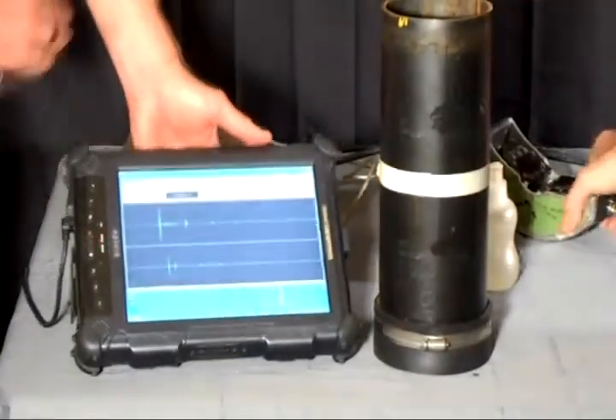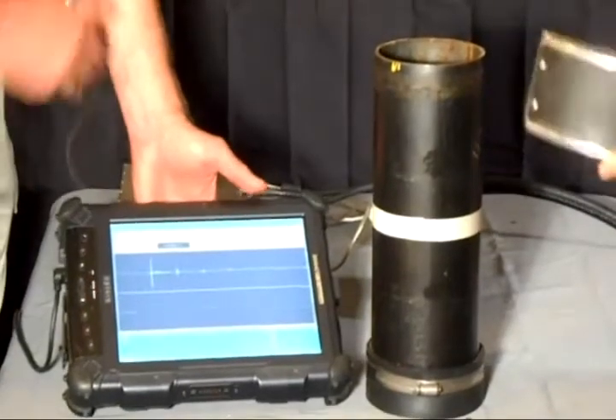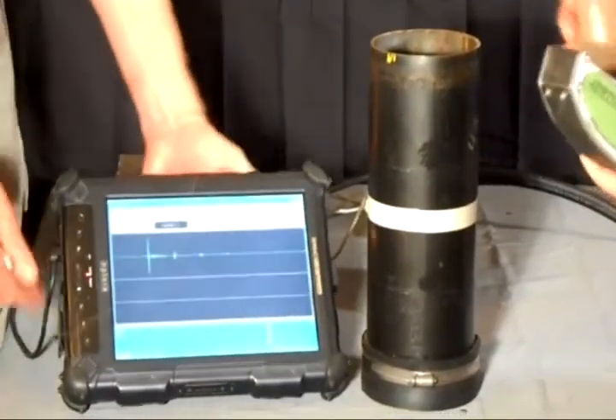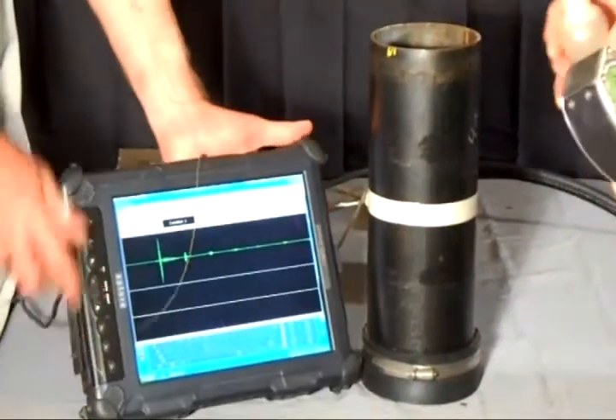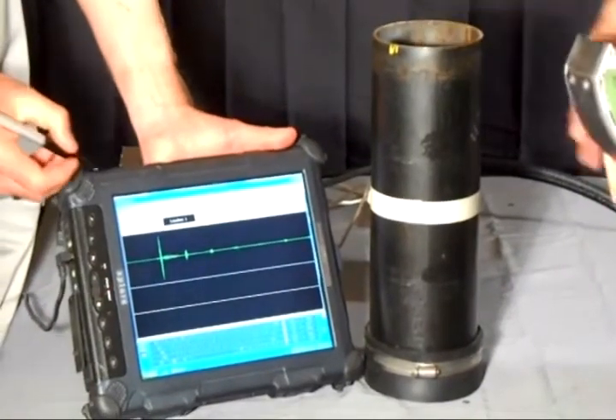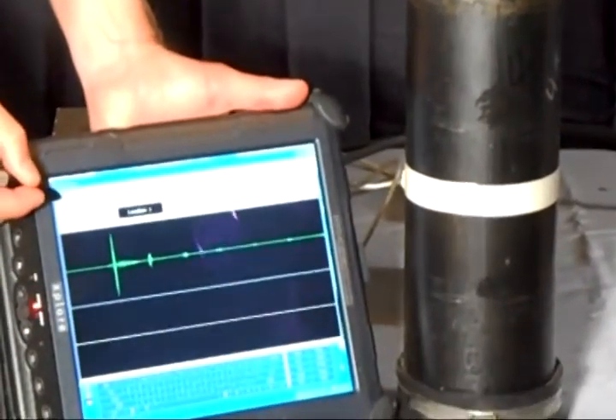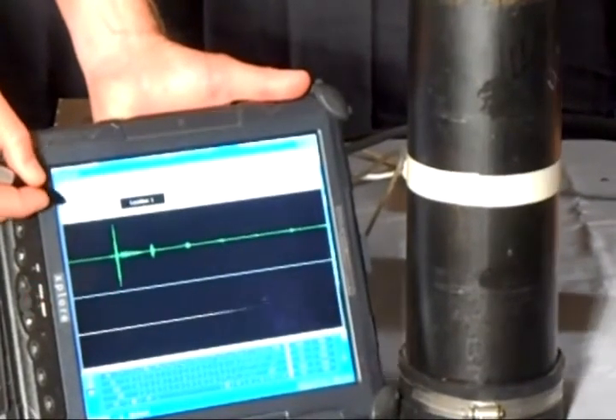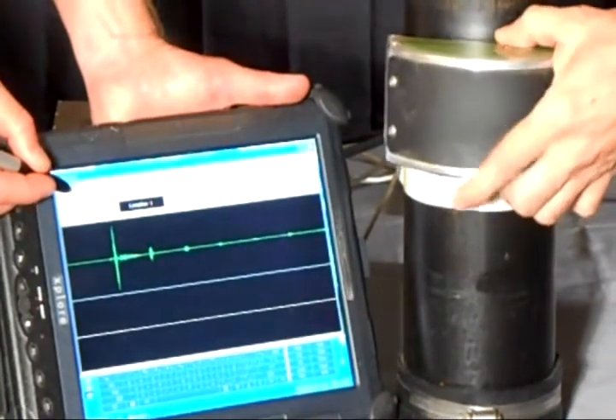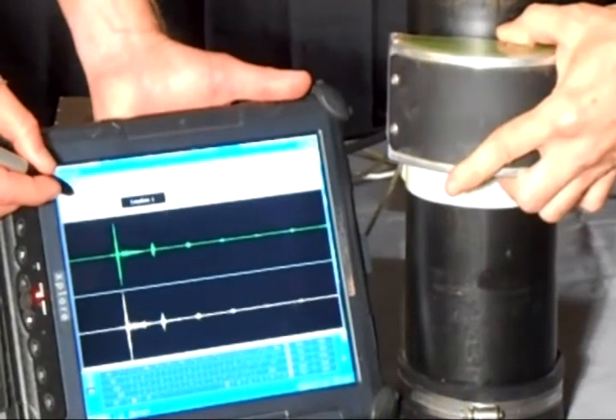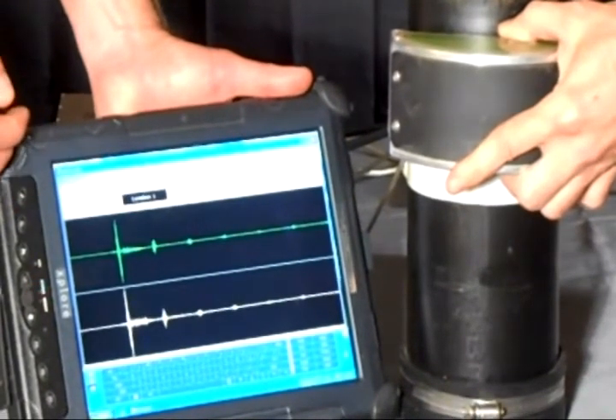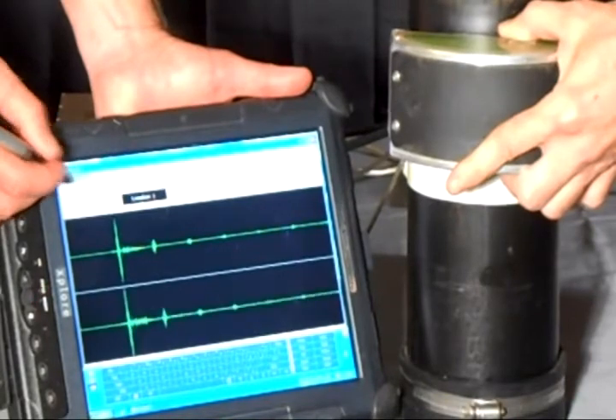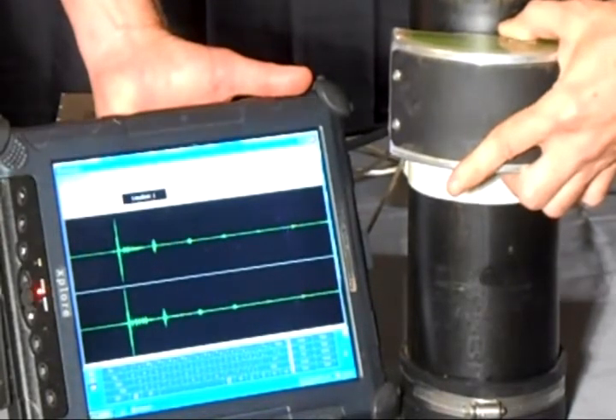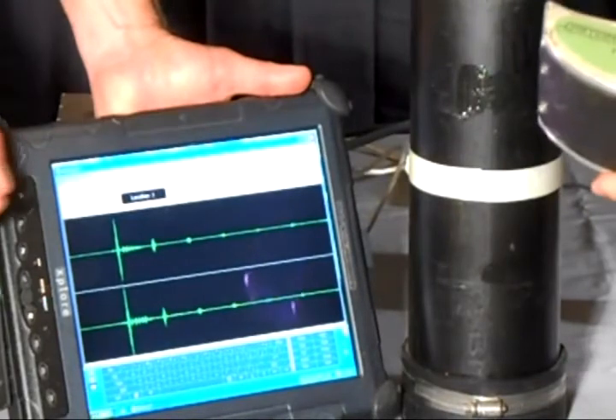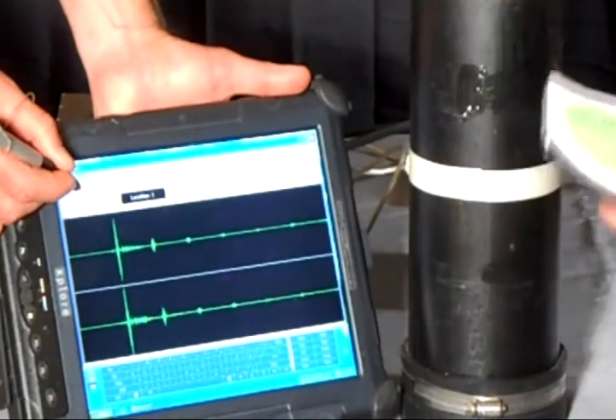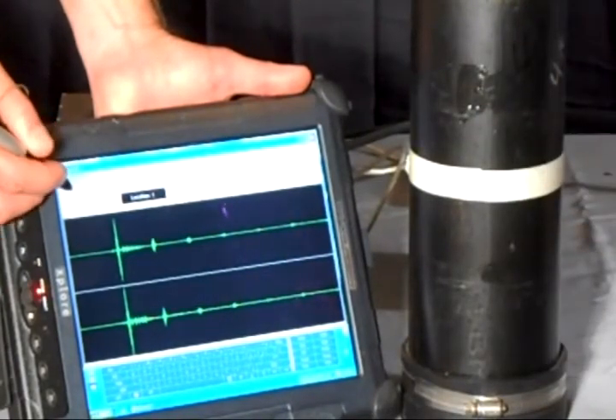We're going to go back to our good piece of pipe. We've got our localized guided wave scanning head, same couplant. What you're looking at on the screen there is the upper signal is what a perfectly good Schedule 10 4-inch diameter pipe waveform should look like on a dry pipe. We'll do a scan here, and as you can see, the waveform that we're measuring on the bottom exactly matches the one on the top, where it's really close. So the important thing is that the waveforms look similar to each other. This would indicate a good dry pipe.